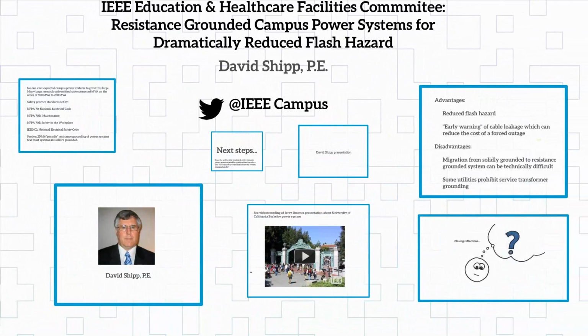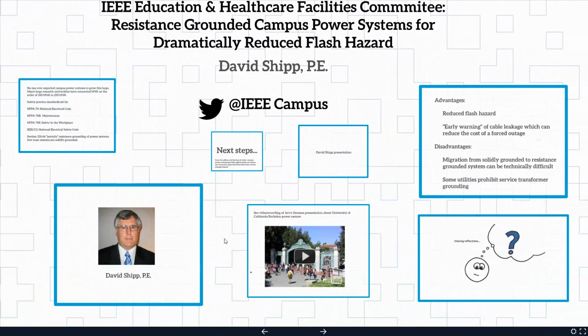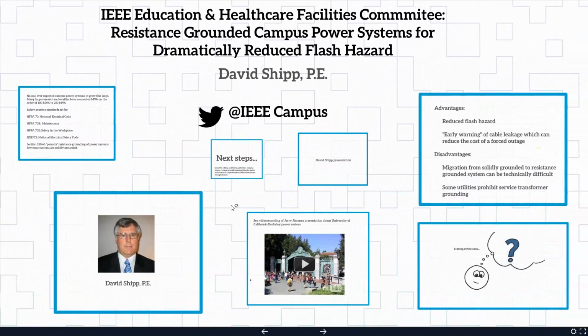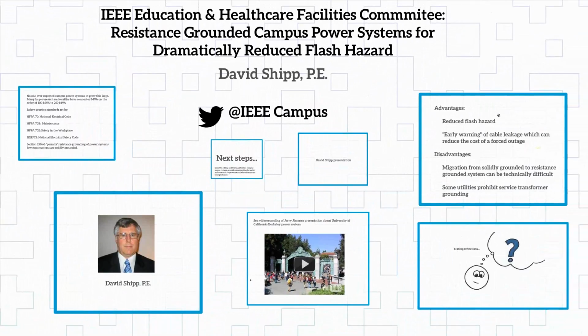I'll take all that copper and throw it away and buy a few 15 kVA isolation transformers to feed your 277 volt lighting, make all the incident energy go down, and save all your copper money. And the safety goes away. Like, for example, panel boards in halls for the lighting. Right. And literally, I actually went through some of this with a consultant a few years ago conceptually. At the very least, it's a break even, but it's dramatically safer.